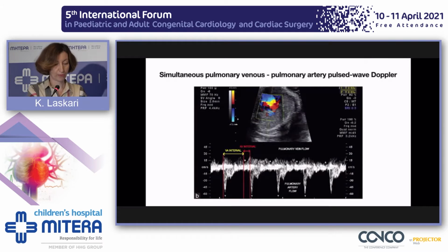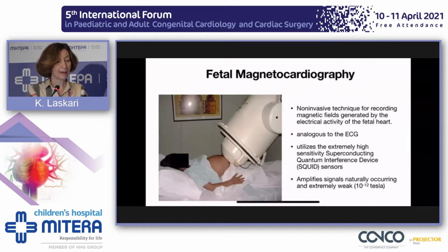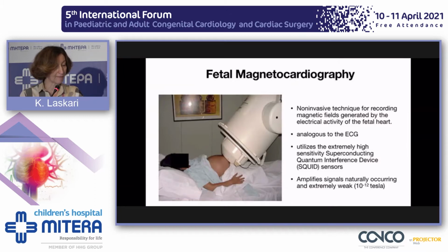Fetal magnetocardiography is a non-invasive technique for recording magnetic fields generated by the electrical activity of the fetal heart. It is analogous to an ECG. It utilizes the extremely high sensitivity superconducting quantum interference device, which can amplify the naturally occurring and extremely weak signals from the fetus.